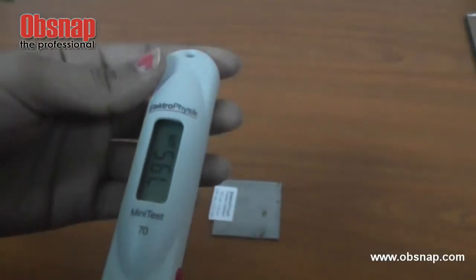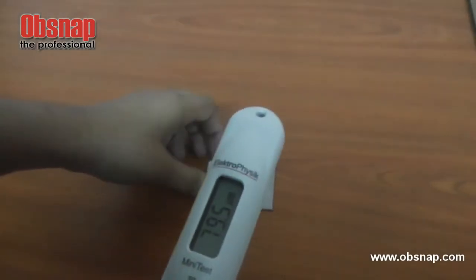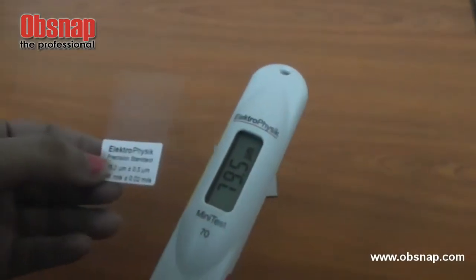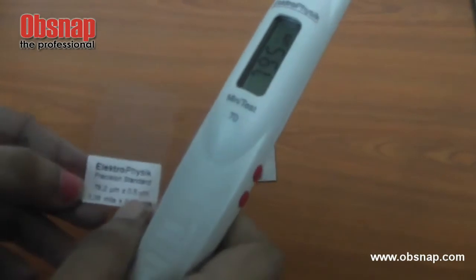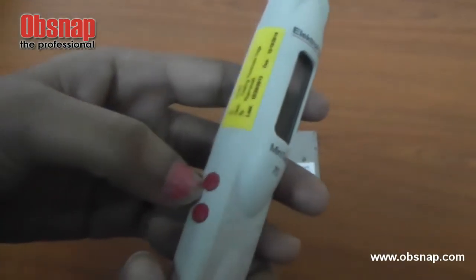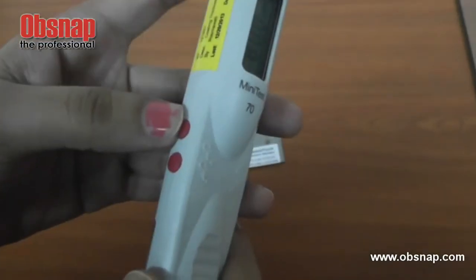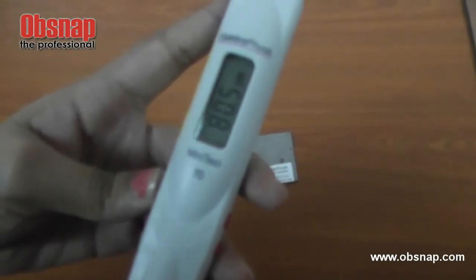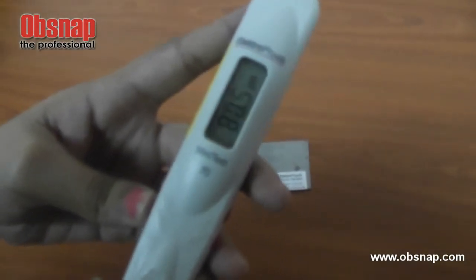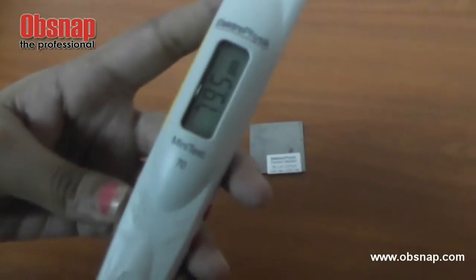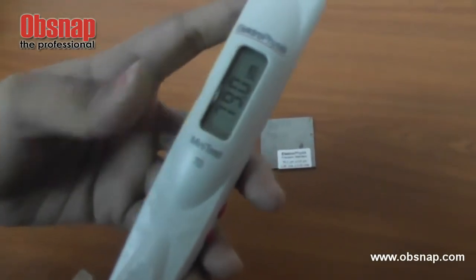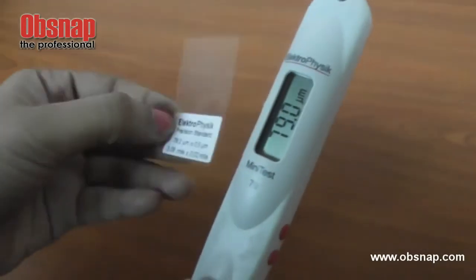If the reading is not according to the precision standard, you can calibrate by just pressing this calibrate button. The top one is calibrate plus, which you can adjust, and the one below is minus. So right now I'm going to adjust to 79.0, which is close to the precision standard.